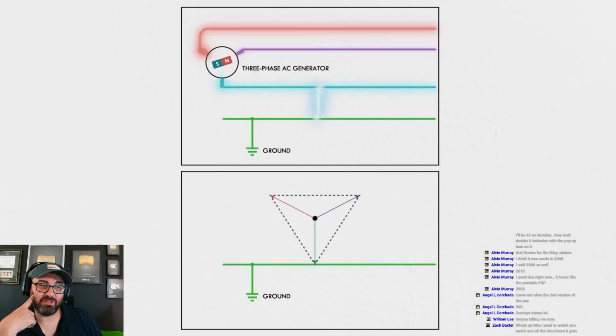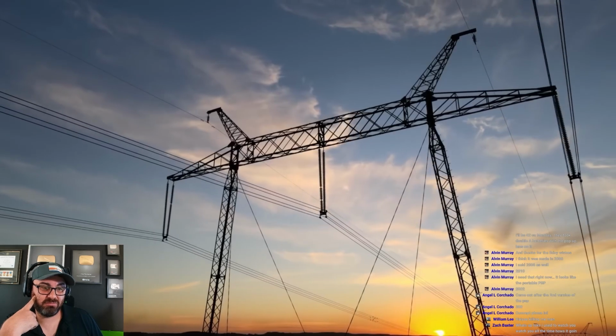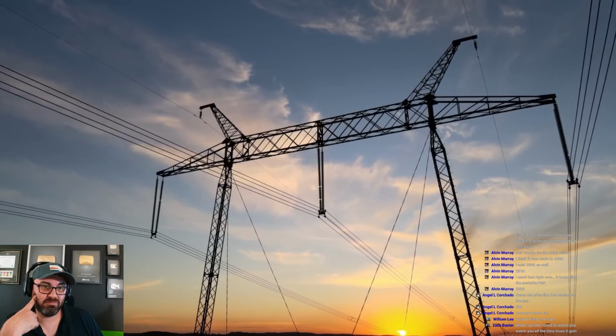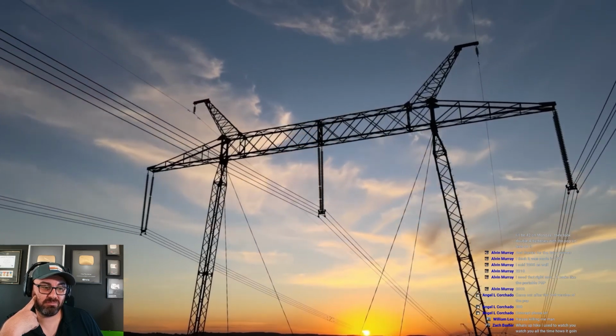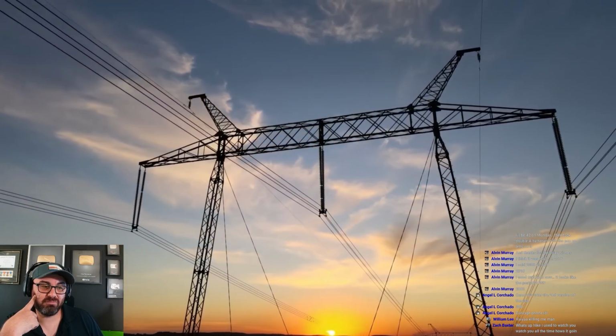In the example I showed, the phase to ground voltages of the two unfaulted conductors rise to almost twice what they would be in a balanced condition. Here's why that matters. Higher voltage requires more insulation, which means more cost. Especially on large transmission lines where insulation means literally holding the conductors great distances away from each other and the ground.